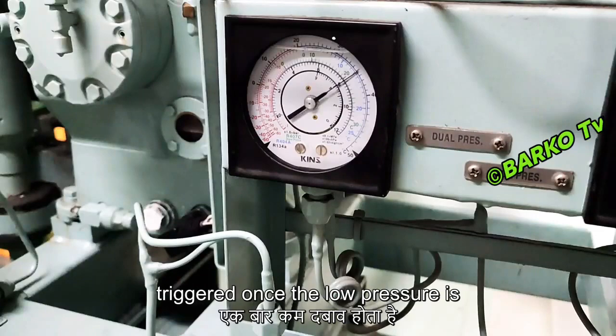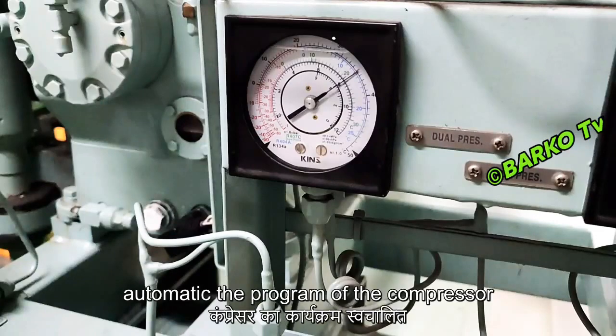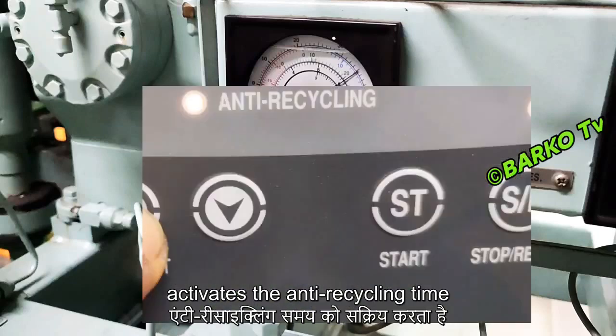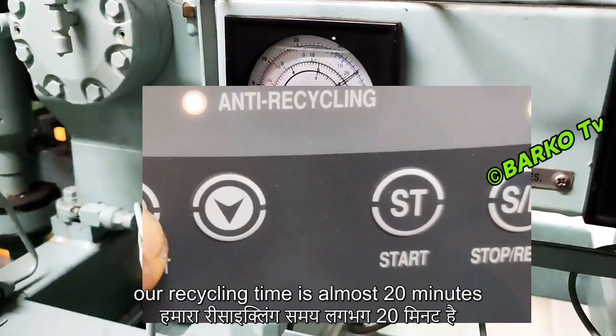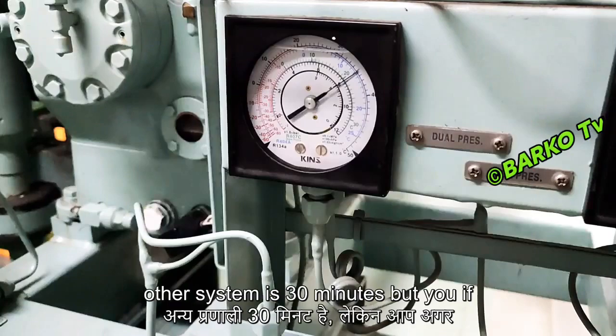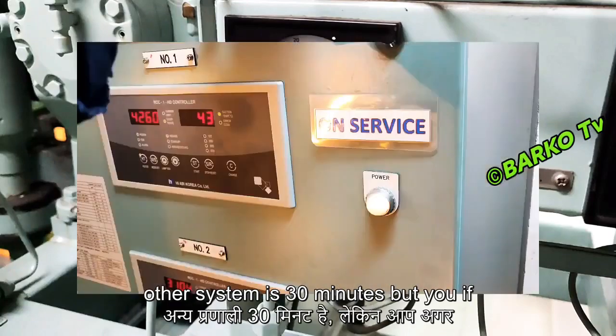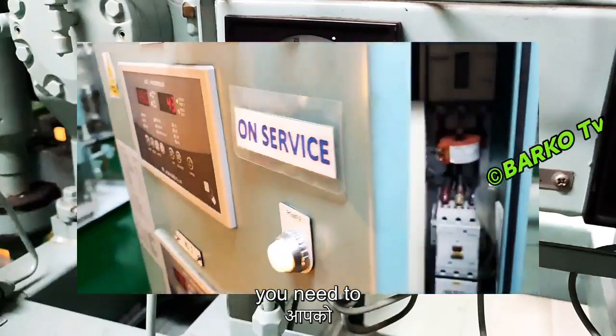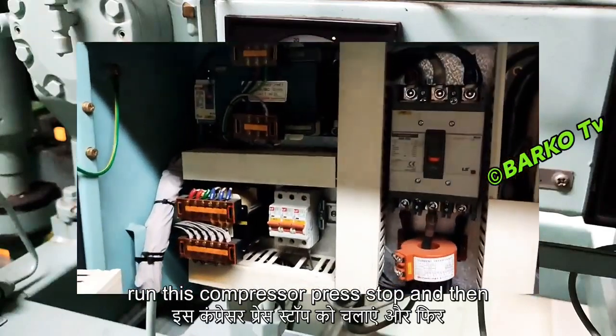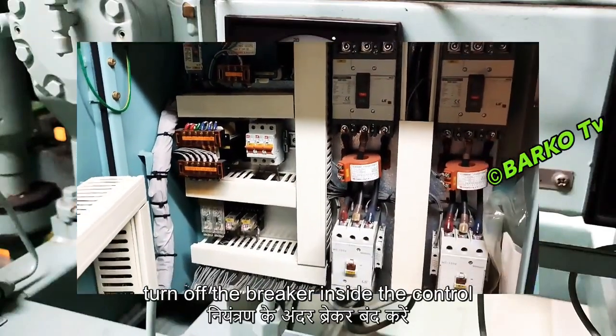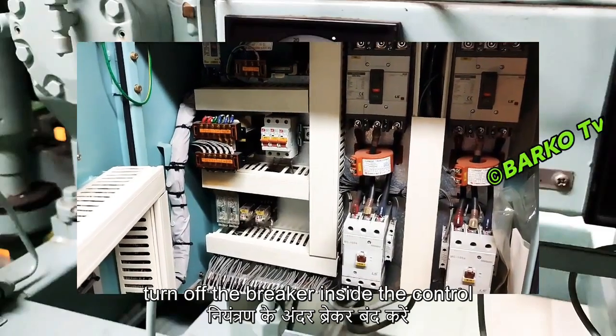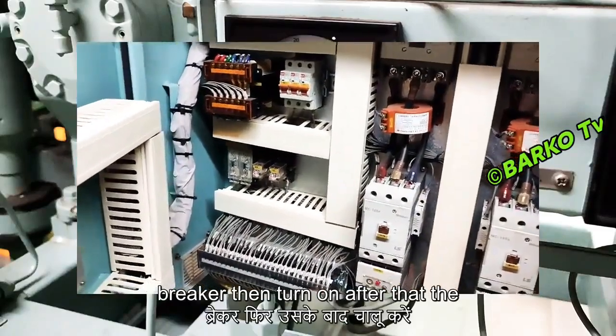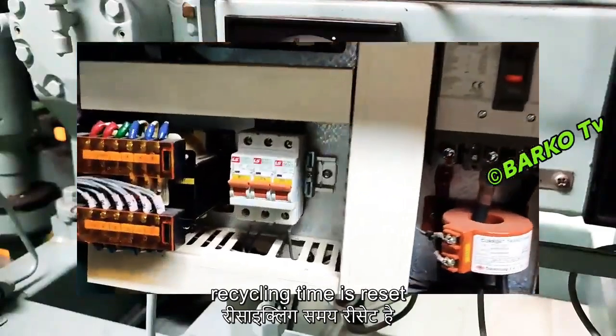Once the low pressure is triggered, the program of the compressor activates the anti-recycling time. Our recycling time is almost 20 minutes. Other system is 30 minutes. But if you need to run this compressor, press stop and then turn off the breaker inside, the control breaker, then turn on. After that, the recycling time is reset.